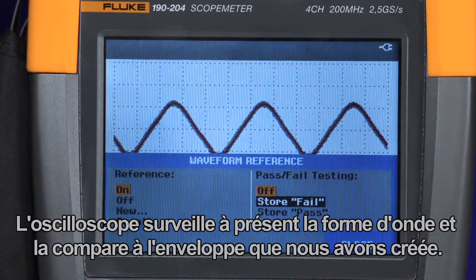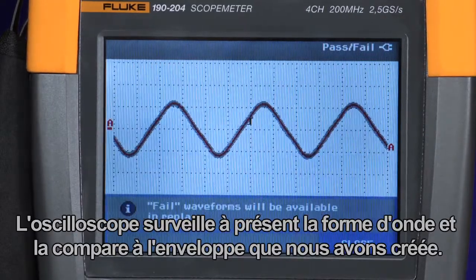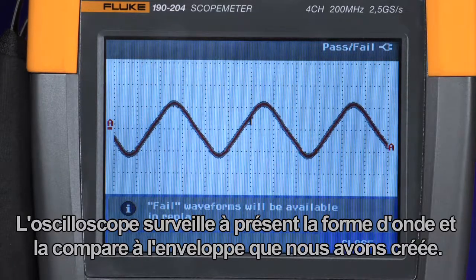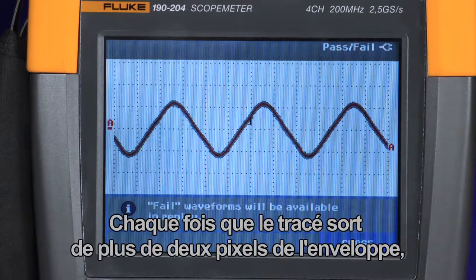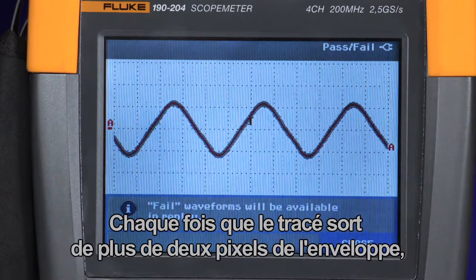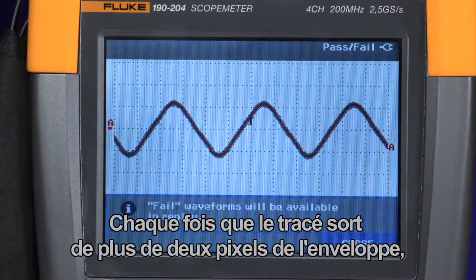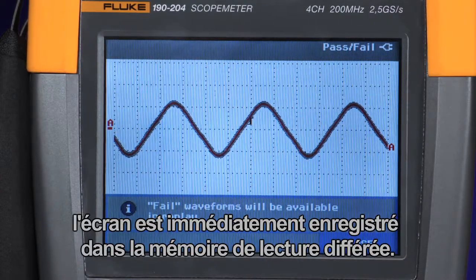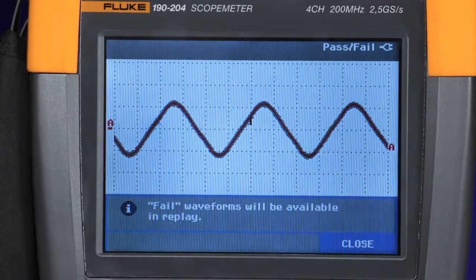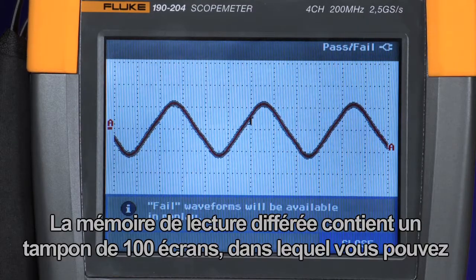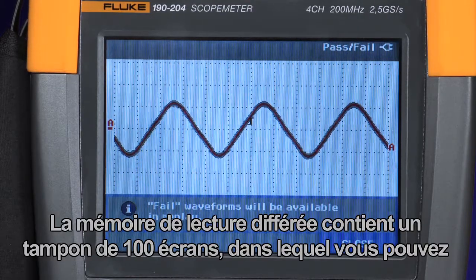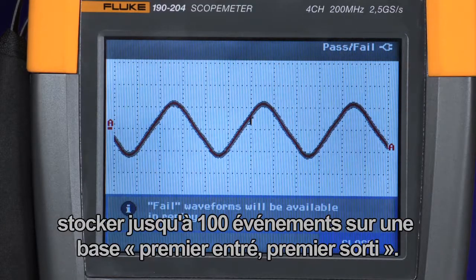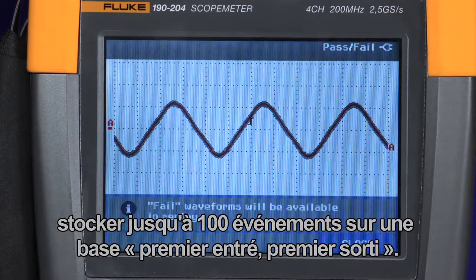Now the oscilloscope will monitor the input waveform and compare it to the waveform envelope that we've just created. Any time a trace falls outside of that plus 2 pixel window, it will immediately capture that screen and store it to the replay memory. In the replay memory, we have a buffer of 100 screens where you can store up to 100 events on a first in, first out basis.